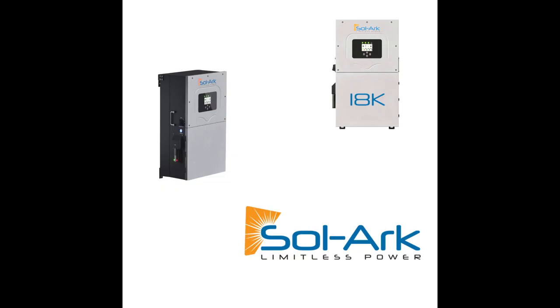This is our outdoor cabinet. So this is our HVR. It is a NEMA 3R enclosure. It's 60 kilowatt hours. And the modules in here are actually a little bit different, which is what allows us to pair either a 30K or a 60K inverter on the cabinet. Mounts right on the side. Again, very small footprint. And one of the cool things about this cabinet is it has built-in HVAC. It's an air-cooled cabinet as well as an additional layer of fire suppression. So not only do we have the fire suppression in the modules, we also have it for the cabinet as well. We have seismic drawings for these already, so they're already pre-engineered. Again, we're kind of lowering the barrier to entry when it comes to designing these systems into your projects.